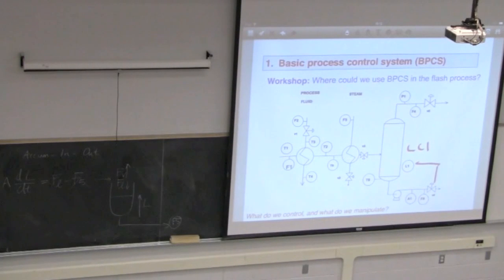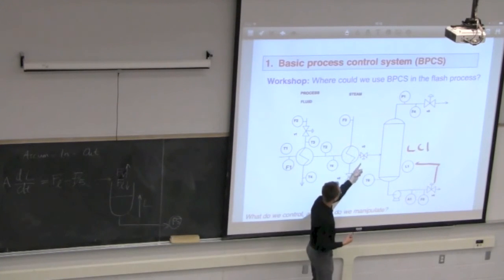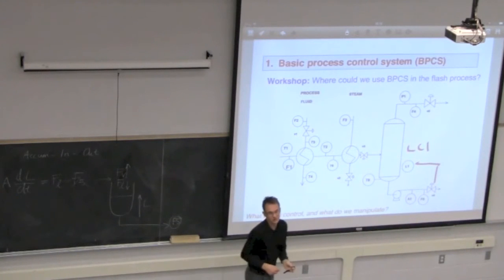So these are things where you're sitting here thinking, oh my God, where was I supposed to learn this stuff? Well, we learn it from these sorts of case studies and experience. So when we're choosing our valve selection, we try not to manipulate valves that are going to throttle and change production levels. We want to keep those constant. So let's select V5 then to control pressure.